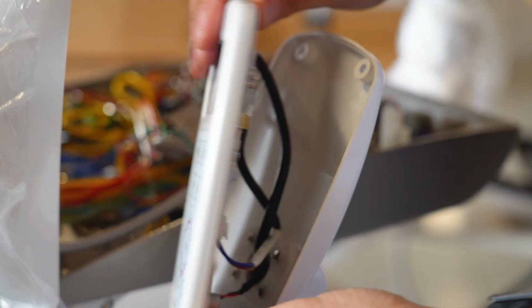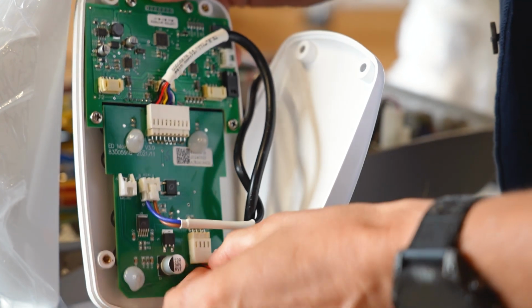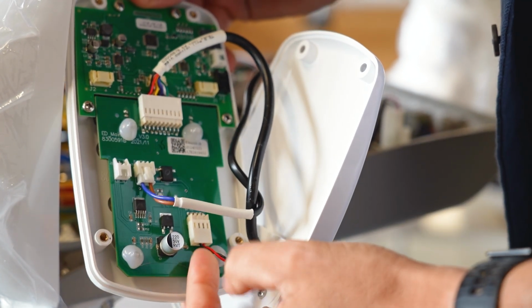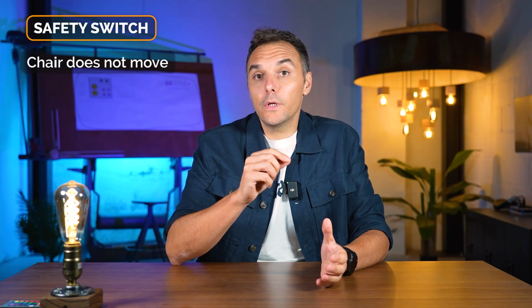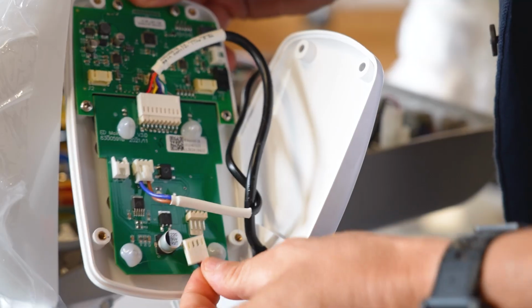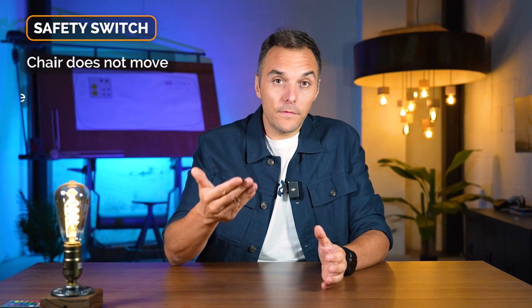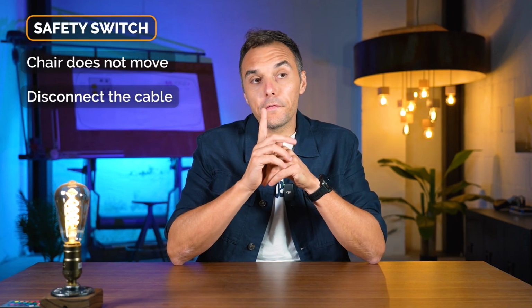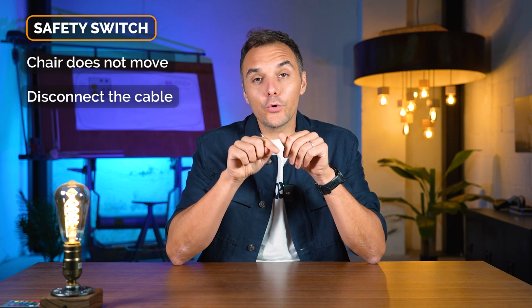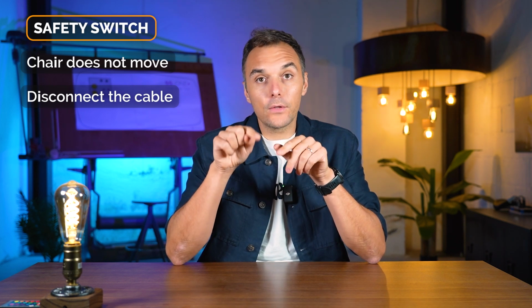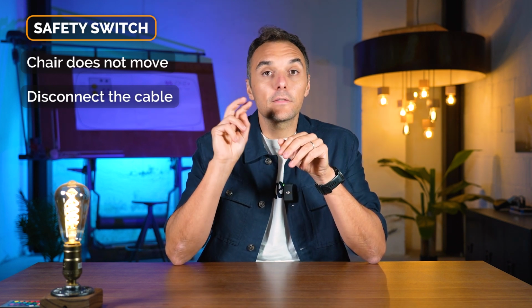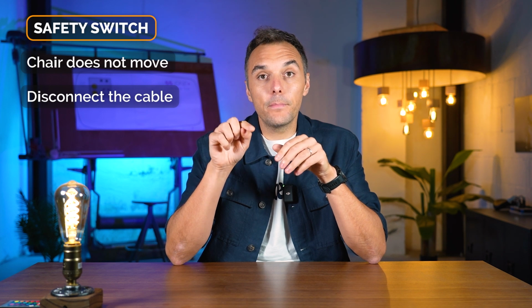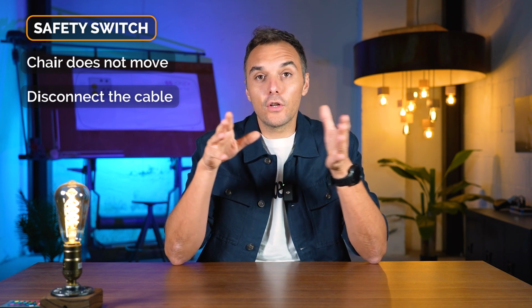The first one: it can be that the activation switch installed on the main board of the control panel on the doctor side is faulty. We need to disconnect that cable and see if the chair is moving. If the dental unit is not moving at all, and when you press one of the movement buttons it only gives a beep beep sound, that's it - the chair is not moving at all.